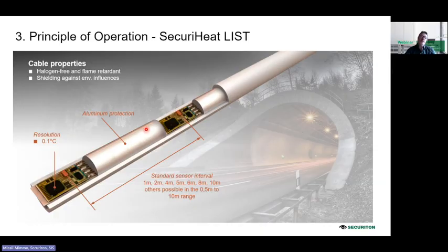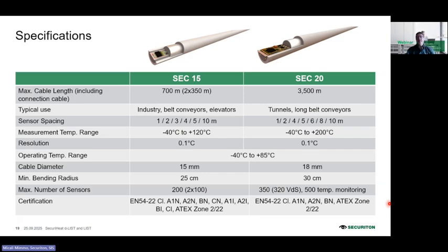We have the aluminum protection inside, which gives a little bit of stability in the cable, but on the other side it's a good conductor for the heat. So in case of a fire in a tunnel, the cable will heat up and the aluminum will help to conduct the heat to the several sensors we have close to this area where we have the warming up. Then a little bit of an overview.